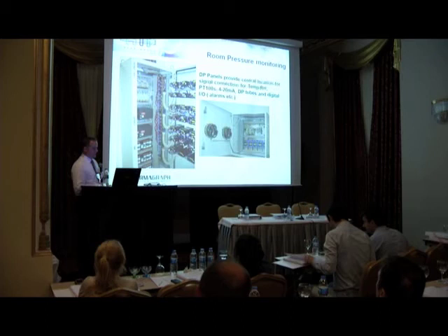Right, so we've touched on the hardware. We really need to look at the software that's associated with it now, because in terms of operators, as far as a facility monitoring system is concerned, this is all you're really going to see. So, the software is 21 CFR Part 11 compliant. It has comprehensive generic validation documents that go with it. It has compliant, non-compliant traffic lights.